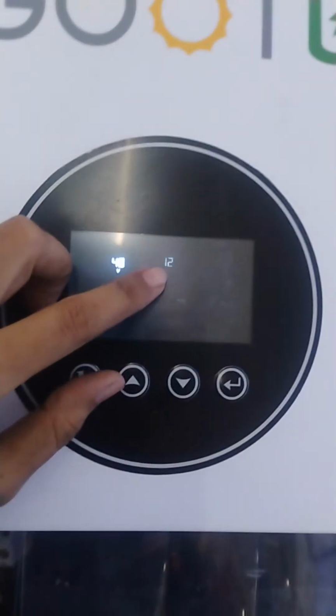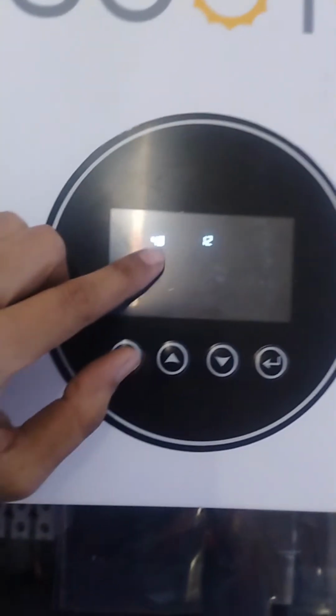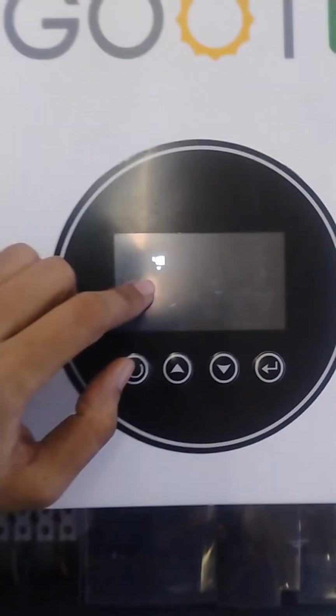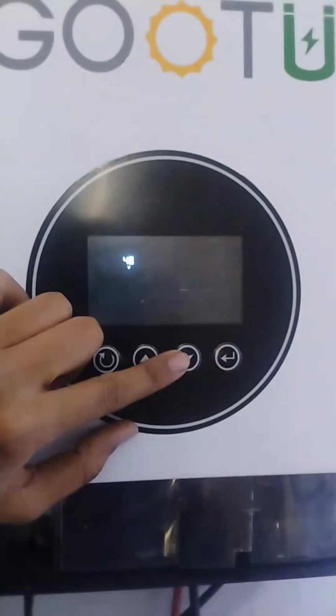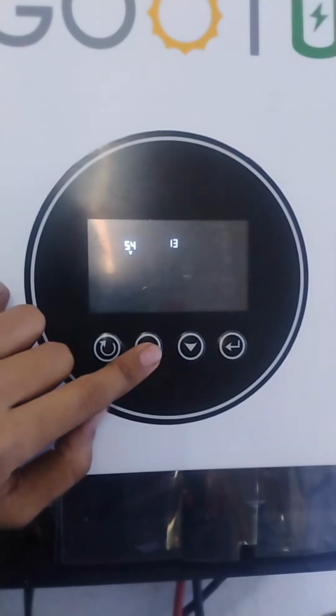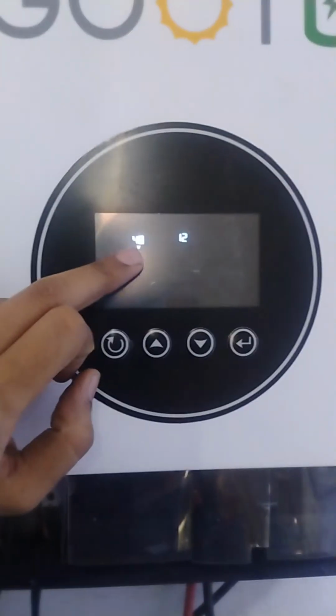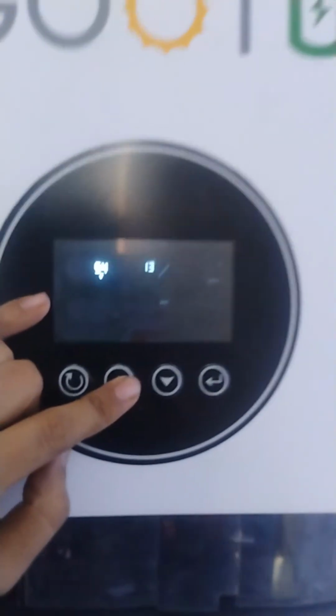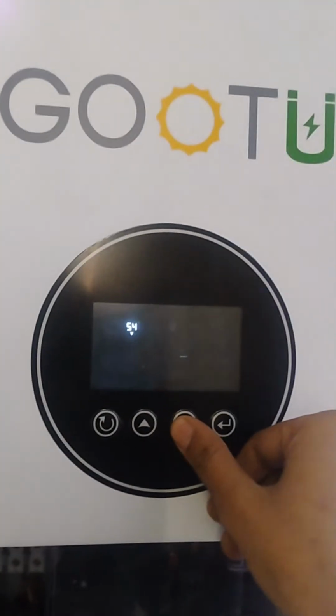In the 12th option, let me turn the page first and explain. The 12th option is the voltage point where the utility source kicks in, as we have selected solar, battery and utility. So when the battery reaches 48 volts, in this inverter when you set it to solar-battery-utility, it will disconnect from battery mode and turn to utility mode. 48 is the maximum power saver mode setting, and with this mode you can select for maximum saving - it's user defined. You can also set it to 44 volts, which is the cutout voltage if you want maximum, but for lithium battery it is not recommended.